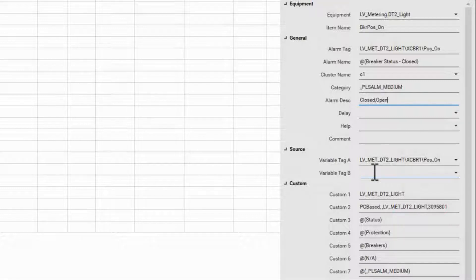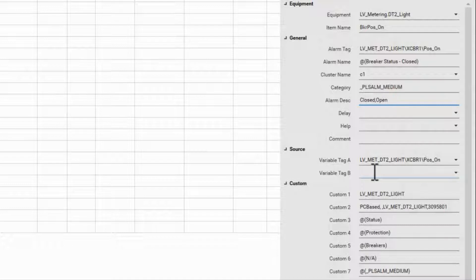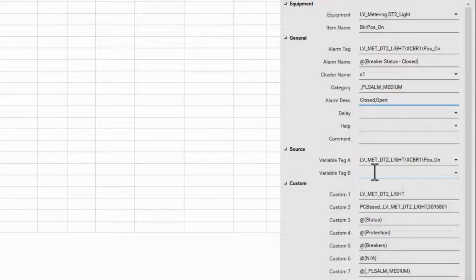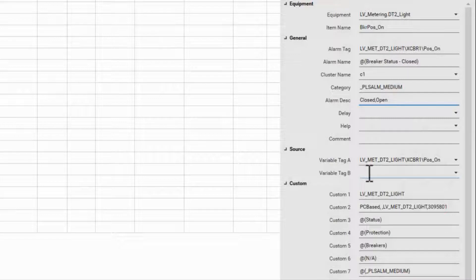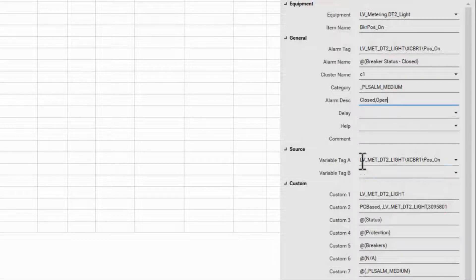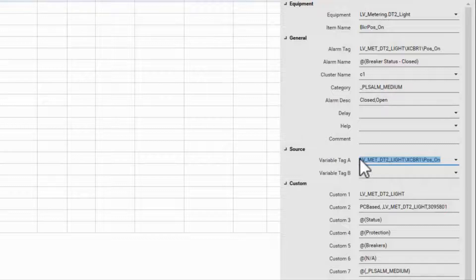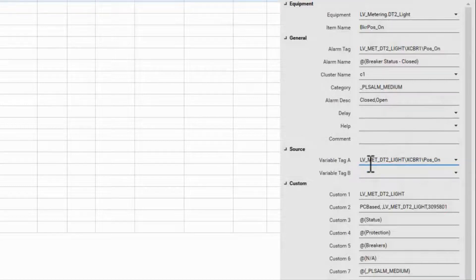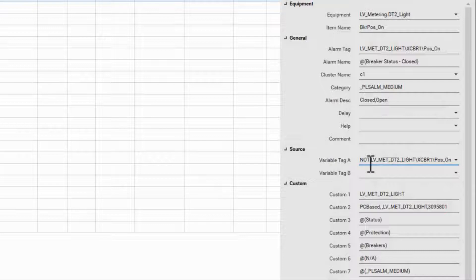For example, if you're monitoring a generator, the limit alarms are only valid while the generator is running. There is one other piece of logic we can add here. If the alarm needs to be inverted from the variable tag, you can add the text NOT in front of the variable tag.